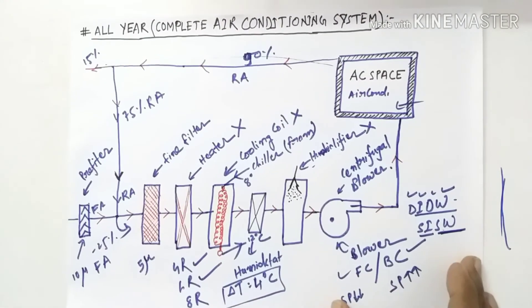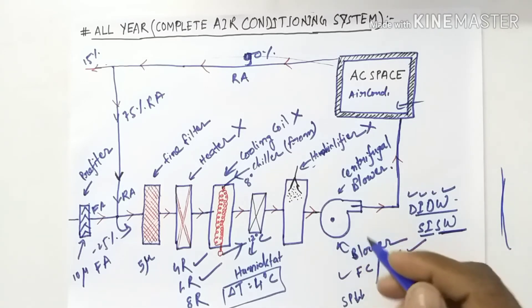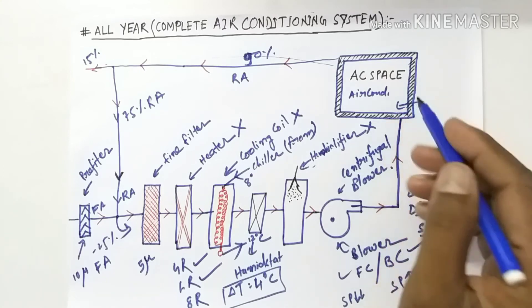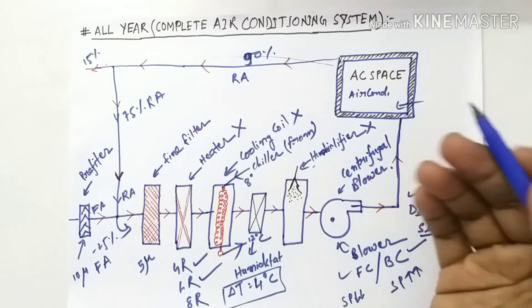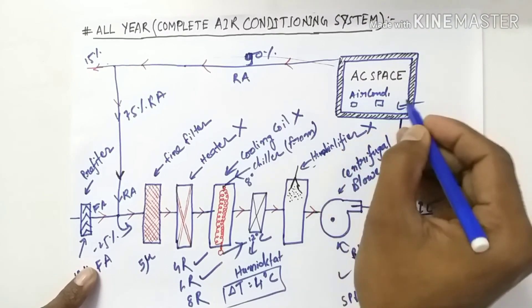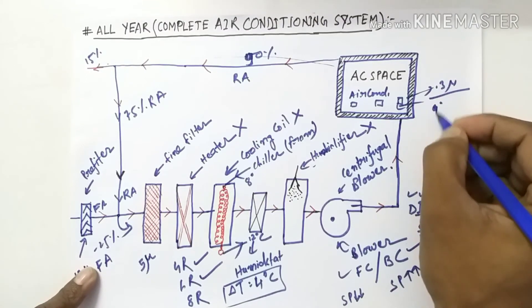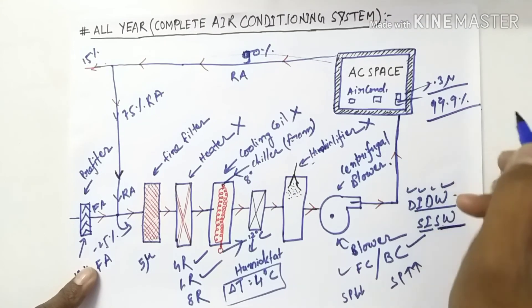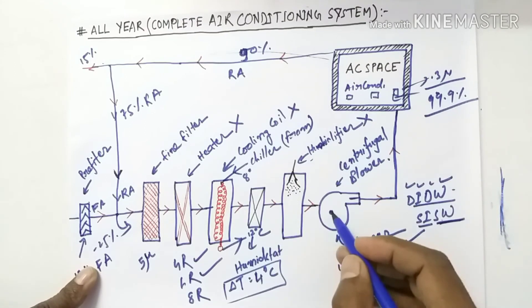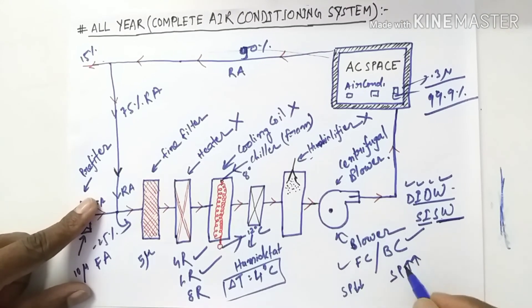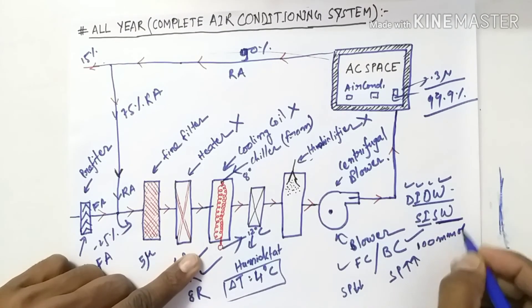This is all about the all-air air conditioning system, and what kind of fan will be selected depends on the air conditioning space. If we put a HEPA filter here, the HEPA filter rating is 0.3 micron with 99.9% efficiency. In that case, we will require a high static pressure blower — meaning the blower will be backward curve and the static pressure will be above 100 mm of water gauge.